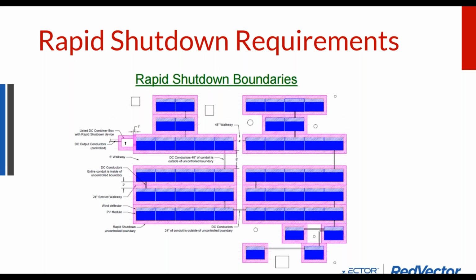But the correct interpretation of rapid shutdown today is that even inside the array, from module to module to module, you have to disconnect that module to module connection. And the reason is, well, you would still have high voltage inside the array. You'd still have 600 volts inside the array. And if the building's on fire, that 600 volt circuit is now ground faulting into the building. And whether that was the original cause of the fire or not, that's still a hazard. So we need to turn the solar panels off if something's going wrong.